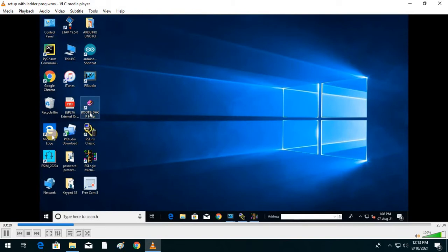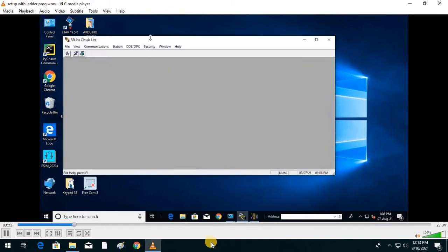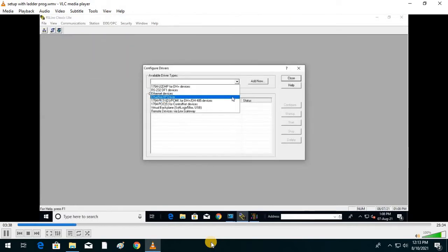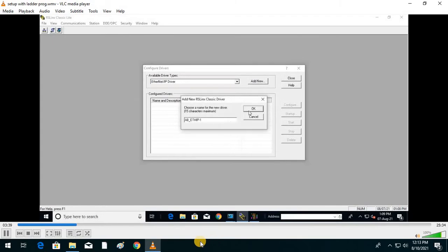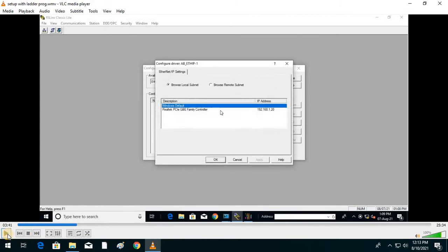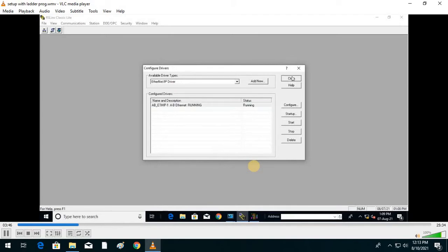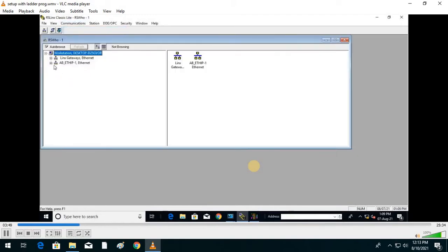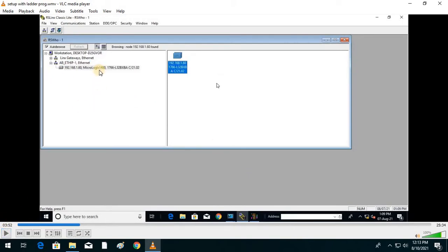In RSLinx Classic, go to Communication, then Configure Drivers. We use the Ethernet driver since an Ethernet connection is given to the PLC. Go to Windows Default, then Apply. Under Communication you can see the Ethernet driver showing 192.168.1.60, which is your MicroLogix 1400 PLC hardware interconnected via the Ethernet port.